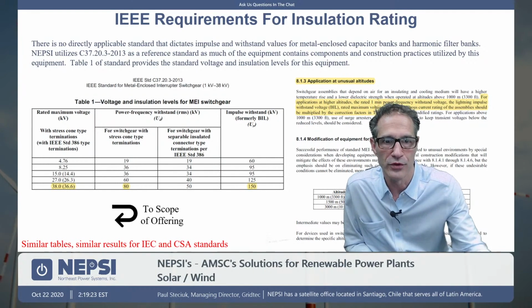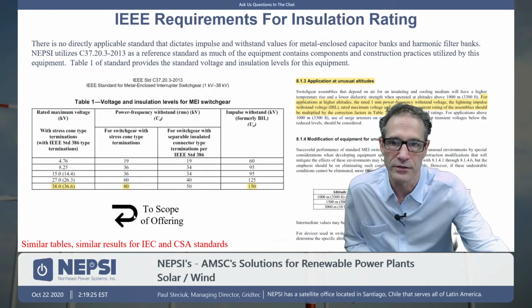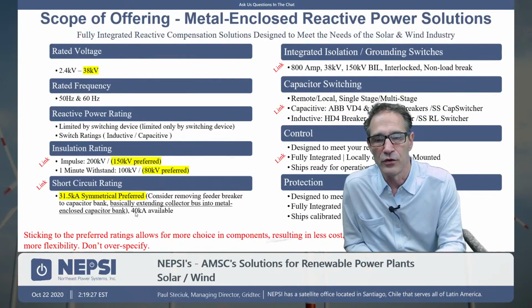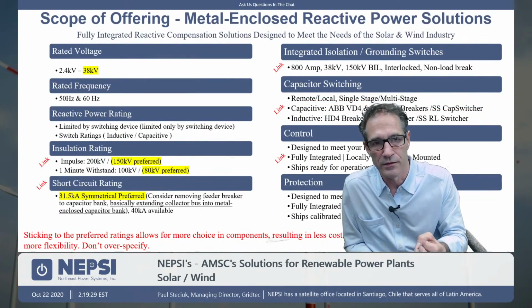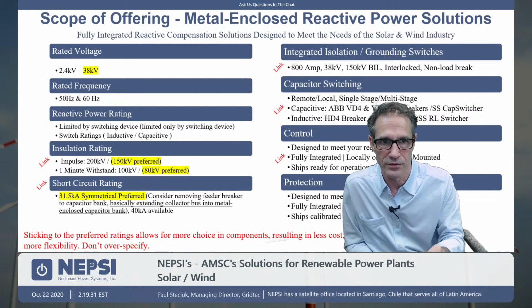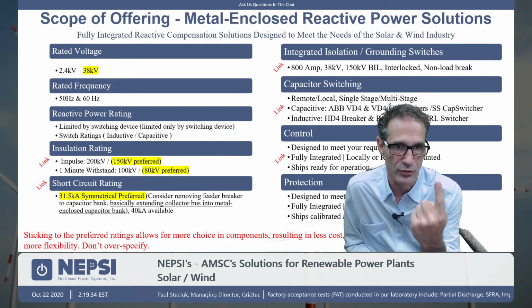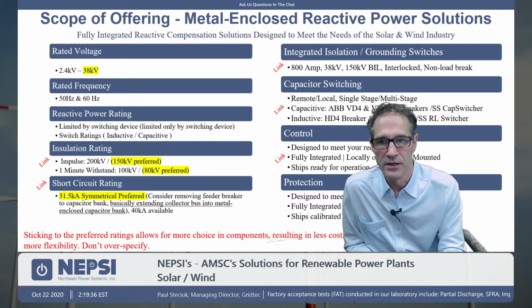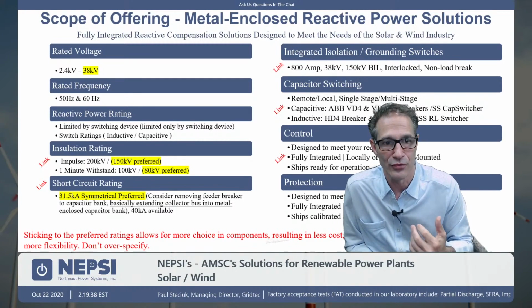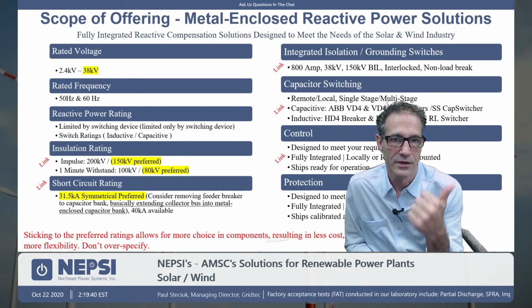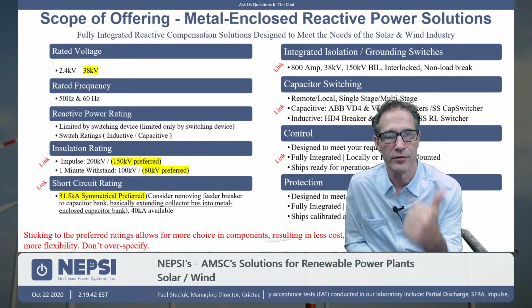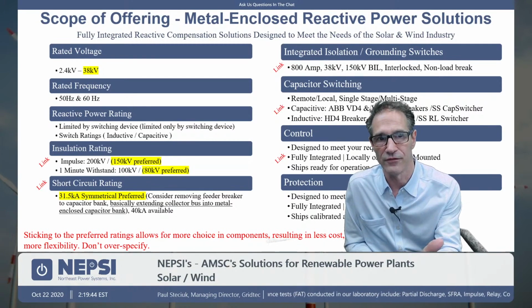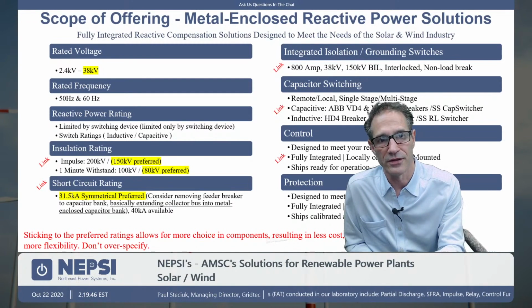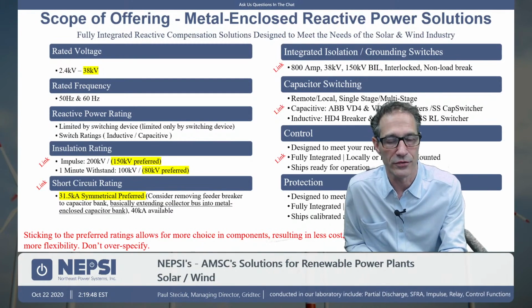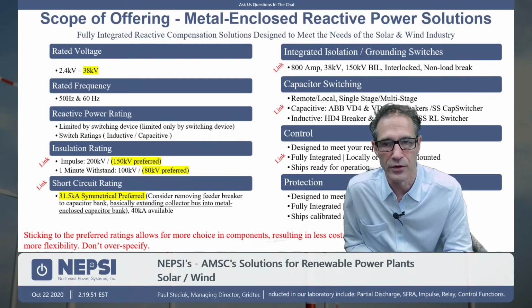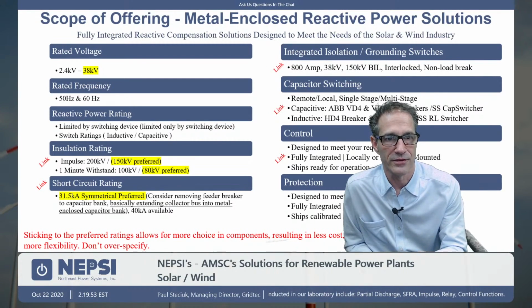150. And there's reasons you want to do that, and the key reason is that if you go to 200, it will squeeze the number of switching devices that can be used. Basically, you're going to push us into one switching device. If we keep it at 150, we're allowed to use breakers. Okay, we can use the ABB VD4, the ABB VD4CS, and the HD4 breakers. Those carry a lower cost than the alternate switching device that we'll talk about in a moment. And oftentimes the lead time is much less.